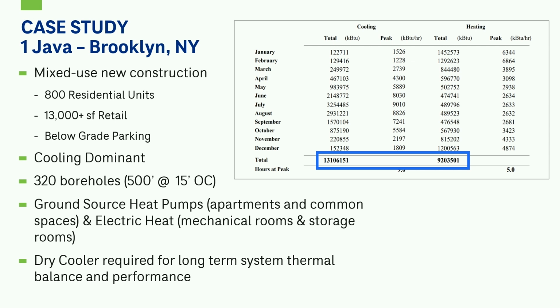So we installed 320 boreholes, 500 feet deep at 15 feet on center. The building is being served by ground source heat pumps in each of the apartments and common spaces. There's electric heat in the mechanical rooms and storage rooms. And then because of this thermal imbalance, we maximized the number of bores that we were able to put in the ground, and then we needed a dry cooler or supplemental equipment for that long-term thermal balance and performance. So we were able to reject some of the heat from the system during cooling, and we wouldn't have too much of a thermal drift in our bore field.